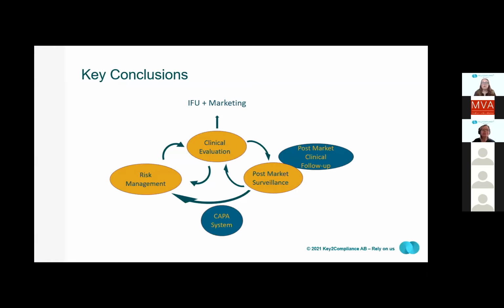As we have heard this morning, there are several parts of your TD that are connected, and you need to look at the complete documentation as a whole and not just as separate parts. In a large organization, this could be quite a big challenge. If we start with the risk management, then we identify all risks and we mitigate them as far as we can. We also include clinical risks and we align those in the risk management with the clinical evaluation. And in turn, the clinical evaluation provides scientific support of the performance of your device. And the clinical evaluation is therefore really the scope of what you can communicate to the user in marketing and IFU, as also earlier talked about as well. And also remember, as mentioned earlier, any residual risks need to be communicated to the user.